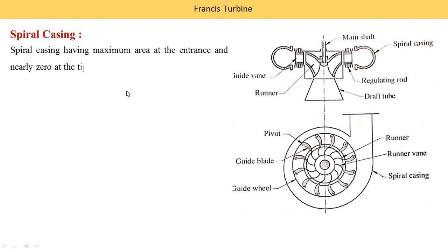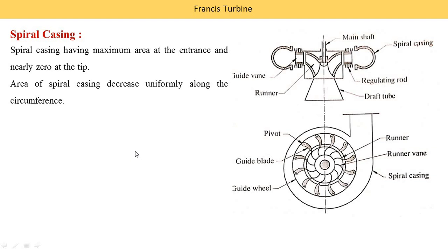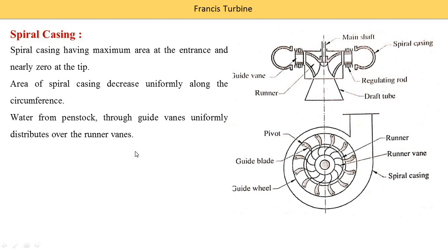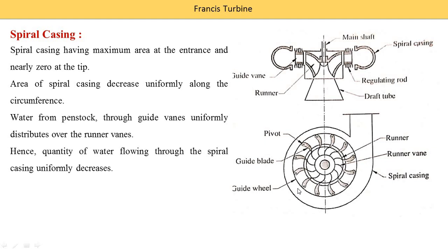Spiral casing has maximum area at the entrance and nearly zero at the tip. Area of the spiral casing decreases uniformly along the circumference. Water from the penstock is uniformly distributed through the guide vanes over the runner vanes. The quantity of water flowing through the spiral casing uniformly decreases because water is continuously supplied through different guide vanes. Area is also reduced, which is why velocity remains constant throughout the spiral casing.